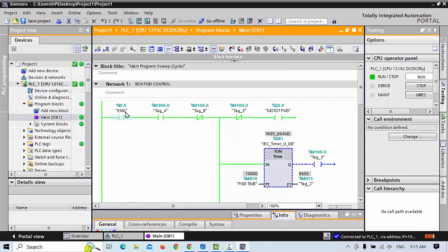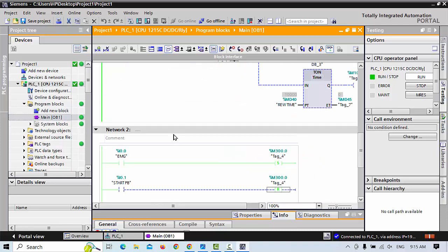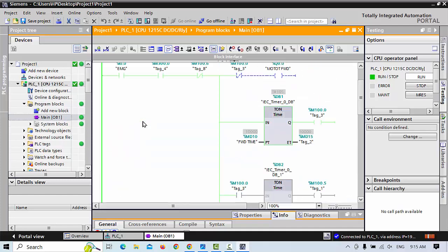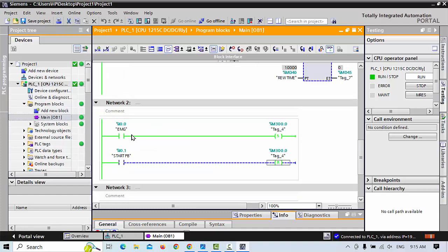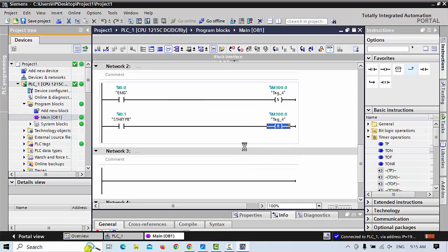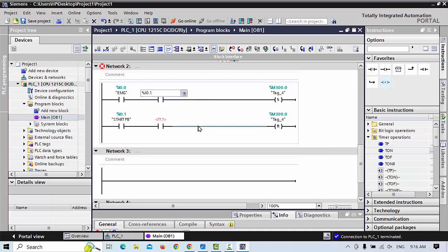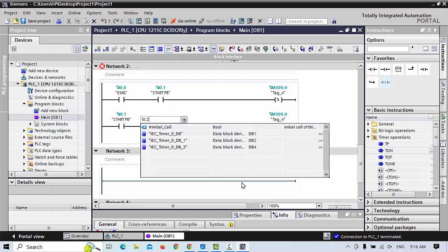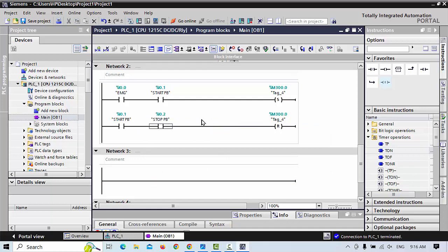But this is one mistake we made. I0.0 is our emergency. We used it in the wrong system. I0.0, when on, after that we have to use this stop execution. After that, here also one more contact we will use: I0.1 for your set condition, and I0.2 is for your reset condition.